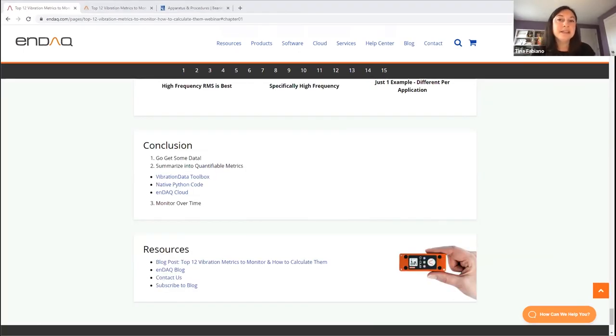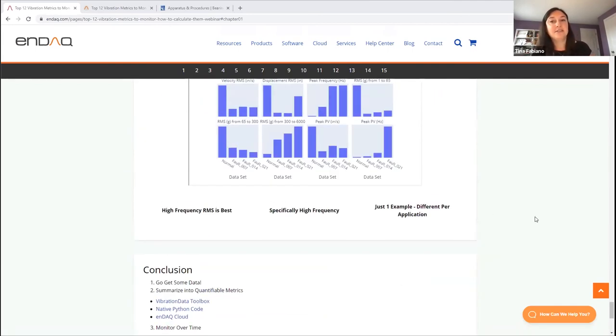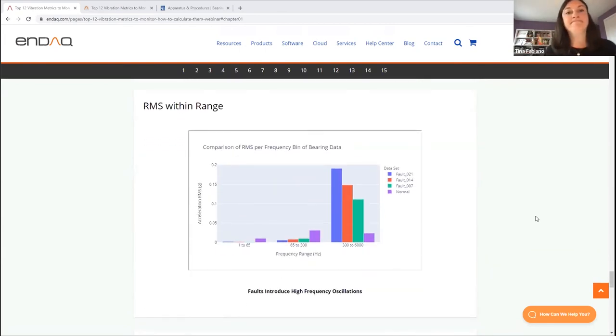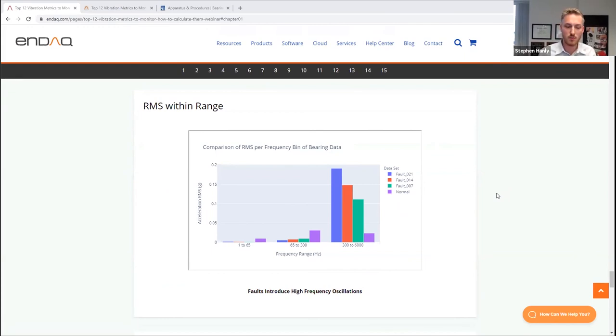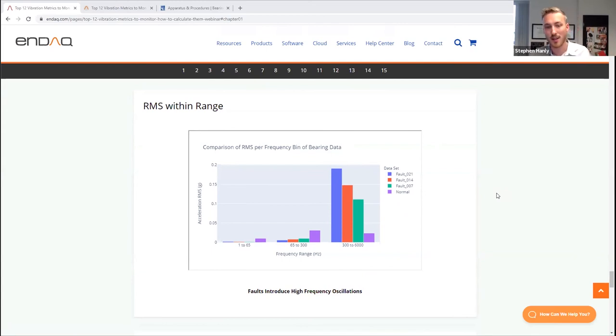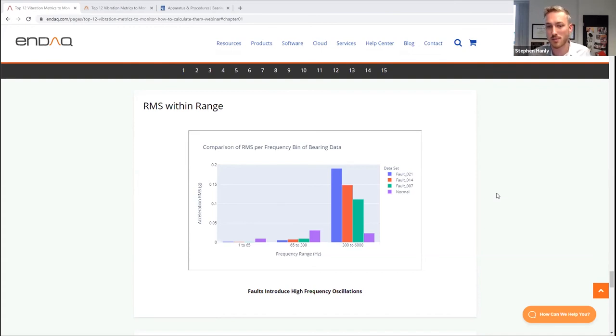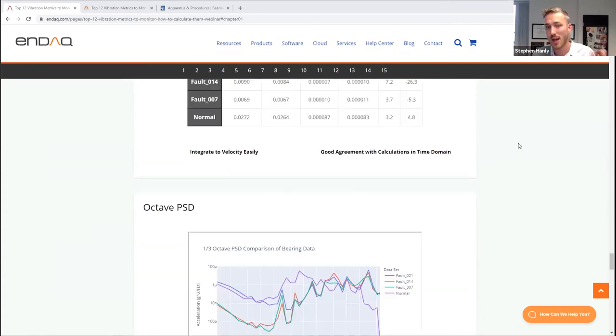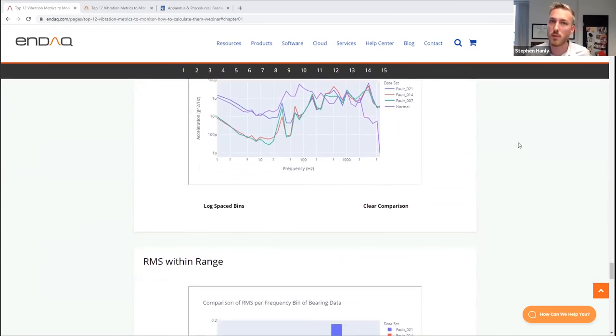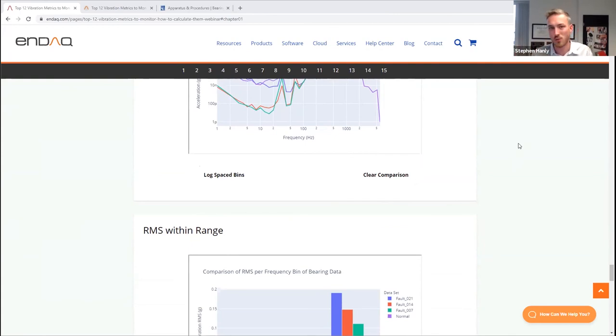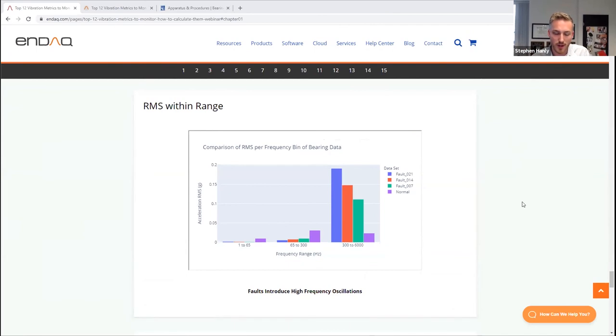Question: Could you explain why you binned the data into 1–65 Hz, 65–300 Hz, and 300–6,000 Hz? These ranges are based on trying to discretely define where a fault condition shows up. RMS levels in the lower frequency range below 65 Hz tend to be related to imbalance; the middle frequency range tends to be related to looseness or misalignment; and the high frequency range is more at the heart of the system's internal health. Once you have the power spectral density, you can define frequency ranges of interest more specific to your application — for example, if you know there's a resonance, you can just track the 10 Hz around that resonance.